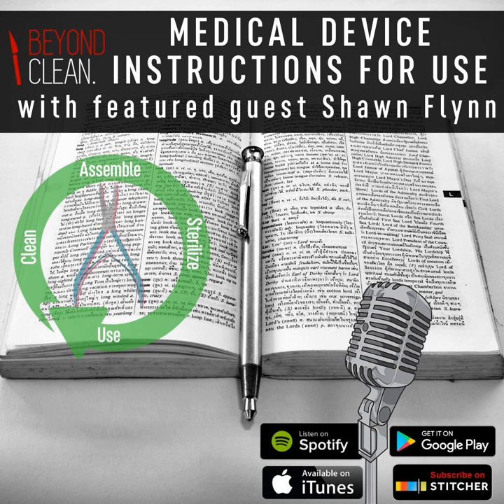The other thing was our device is a class 2 device. It's really the first containment device that has an organizational aspect to it, tying in with point of use cleaning in the OR, where the OR techs are supposed to wipe down and decontaminate their instruments as they go through the case to concluding it. They would then use our device, an apparatus that attaches to the actual containment device itself and opens all the ringed handle instruments. So from a 510 standpoint, that's a class 2 device.